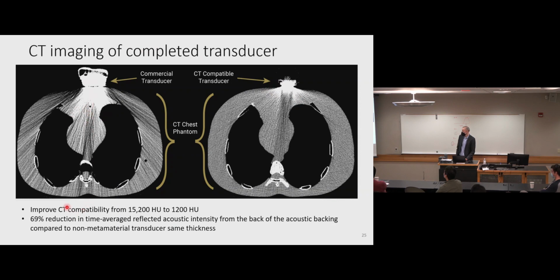And like I mentioned earlier, we've improved the CT compatibility by about an order of magnitude in terms of the Hounsfield units. In fact, what we found at this point is that when we started here on the left with this commercial transducer or any version of this transducer that we could build, the main source of the lack of CT compatibility was due to the acoustic backing, because it's so much of the volume of the transducer and because the density is so high.